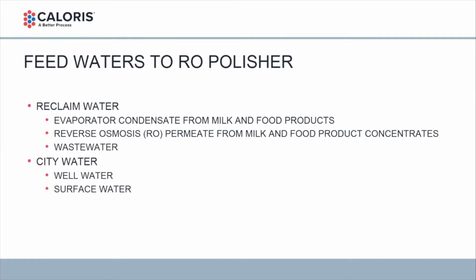The reason we're talking about city water is that at times the city water might be a filler when the reclaimed water does not fully meet the demand. The plant might need so much water a day, and if the reclaim doesn't fill that up, we take city water and clean up the total dissolved solids out of that. City water could be from a well water source, or from a surface water source, a local lake, a river, or whatever.